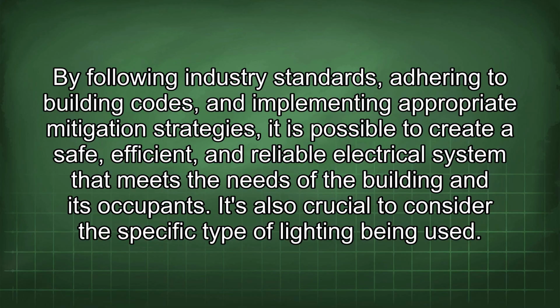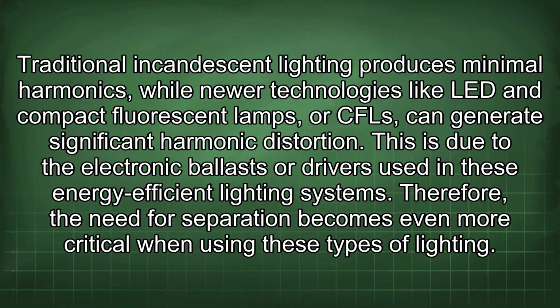It's also crucial to consider the specific type of lighting being used. Traditional incandescent lighting produces minimal harmonics, while newer technologies like LED and compact fluorescent lamps, or CFLs, can generate significant harmonic distortion. This is due to the electronic ballast or drivers used in these energy-efficient lighting systems. Therefore, the need for separation becomes even more critical when using these types of lighting.